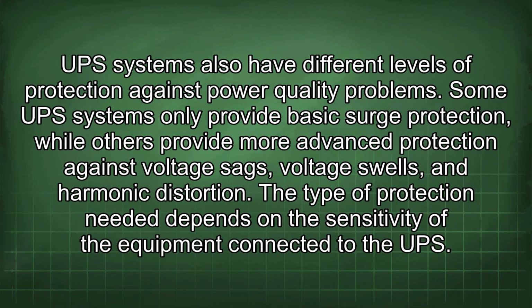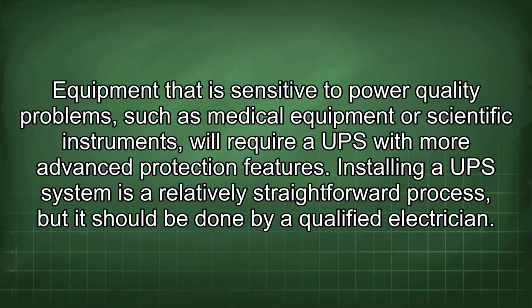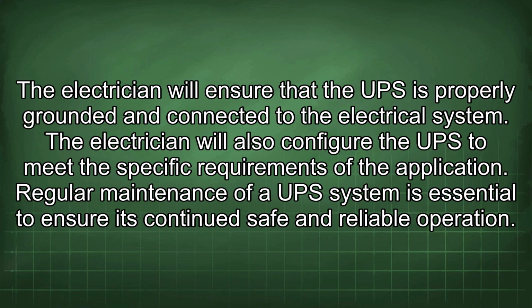UPS systems also have different levels of protection against power quality problems. Some UPS systems only provide basic surge protection, while others provide more advanced protection against voltage sags, voltage swells, and harmonic distortion. The type of protection needed depends on the sensitivity of the equipment connected to the UPS. Equipment that is sensitive to power quality problems, such as medical equipment or scientific instruments, will require a UPS with more advanced protection features. Installing a UPS system is a relatively straightforward process, but it should be done by a qualified electrician. The electrician will ensure that the UPS is properly grounded and connected to the electrical system. The electrician will also configure the UPS to meet the specific requirements of the application.